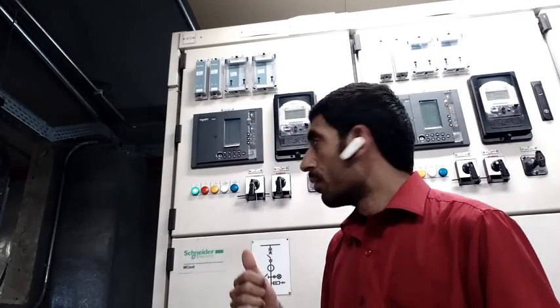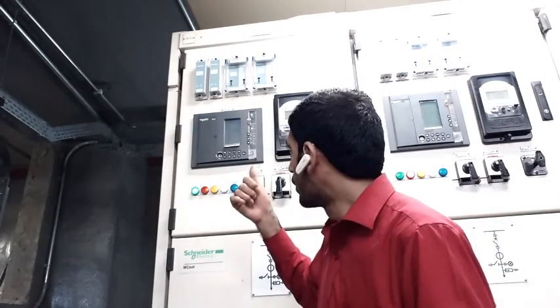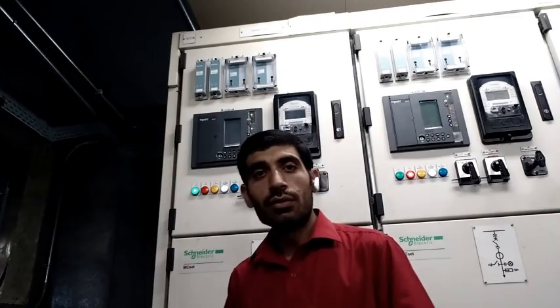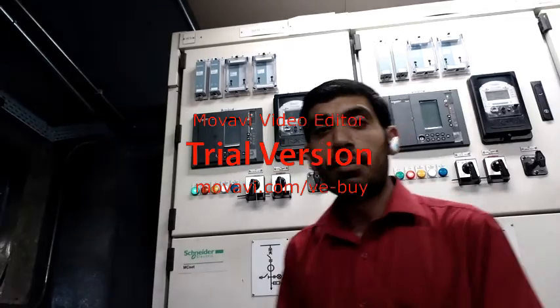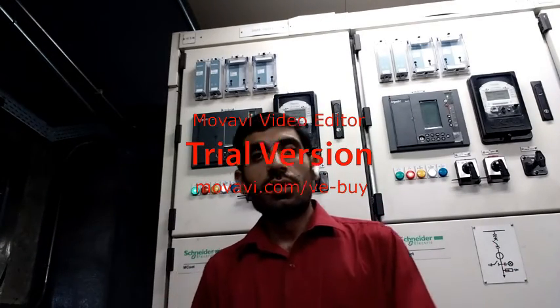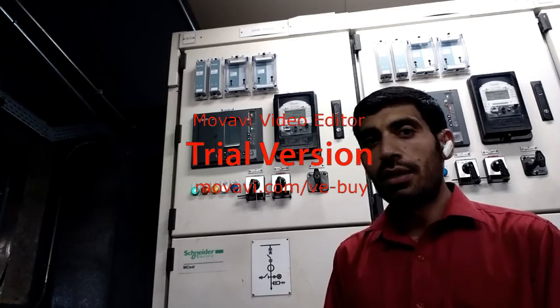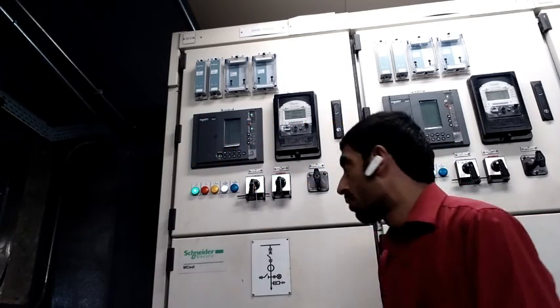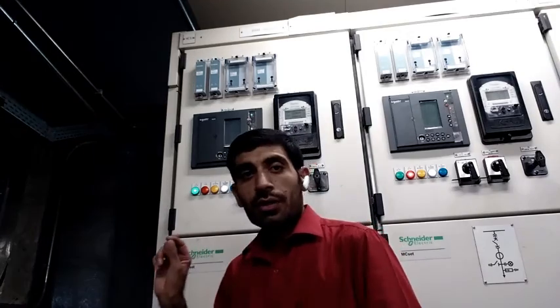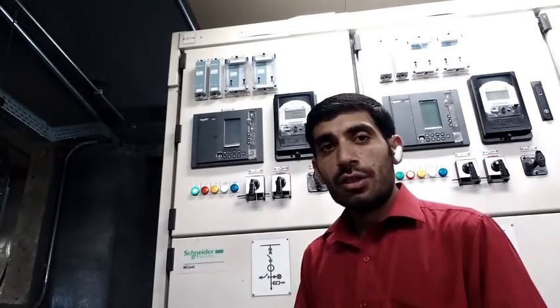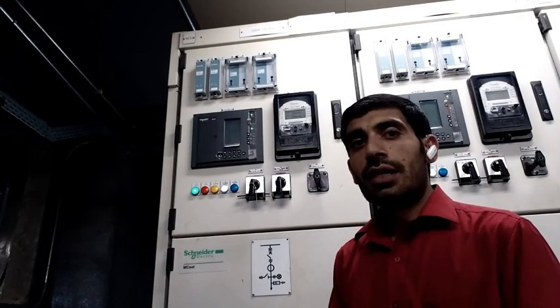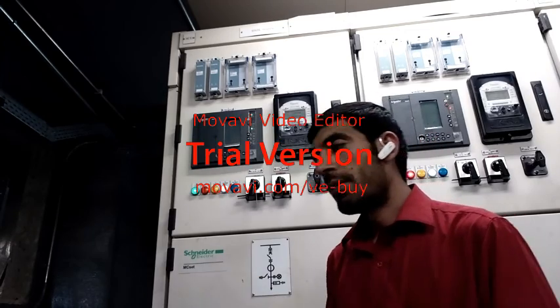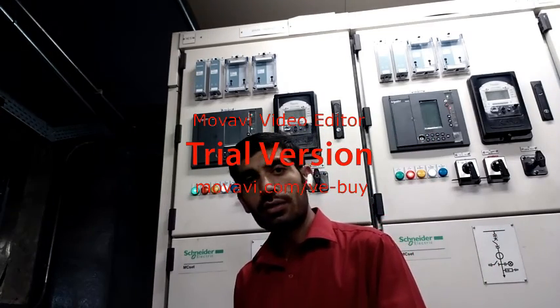And we also use it for under voltage and over voltage, with the selected rated voltage in this relay set at plus and minus 10%. If my voltage increases up to 10%, that means this relay will give an alarm for over voltage and will be tripped within the selected timing. For example, my selected timing is 7 seconds. So within 7 seconds this relay will be tripped.